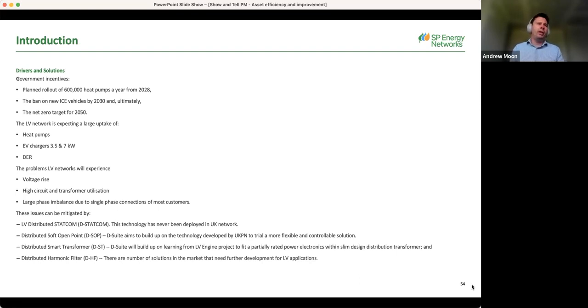At domestic level, EV chargers will be 3.5 and 7 kilowatts, along with things like photovoltaic panels - I doubt we'll see wind, but mainly photovoltaics. When we increase penetration levels of things like PV, we see voltage rise issues and difficulty maintaining statutory limits towards the end of the feeders, especially on radial circuits.